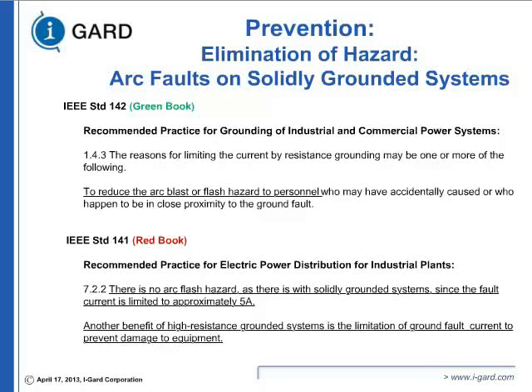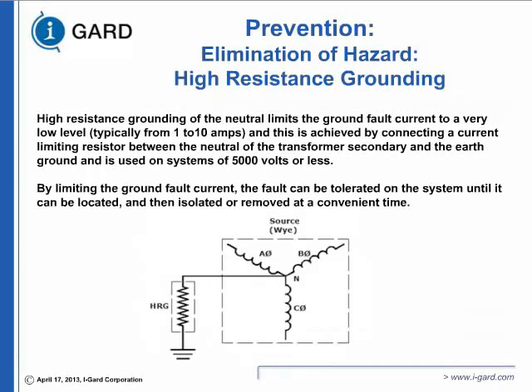The Red Book, IEEE Standard 141, says something similar. There is no arc flash hazard as there was with a solid grounded system, since the fault current is limited to approximately 5 amps. In Canada, I believe they limit it to 10 amps. Another benefit of a high resistance grounding system is limitation of ground fault current. So equipment is repairable. Even if you decide to trip, there is no pressure, there is no requirement that you continue operation. You can trip it, but the damage will be minimal. Elimination of hazard, high resistance grounding system.